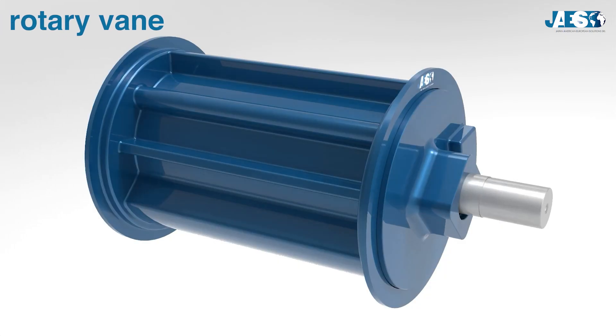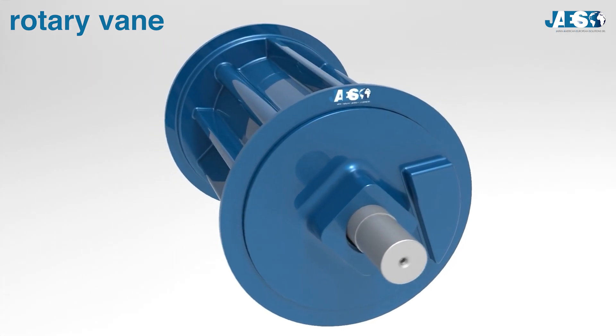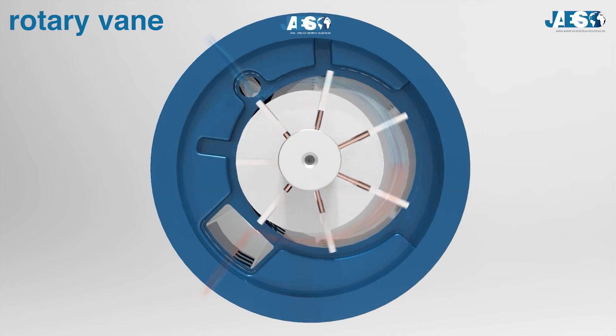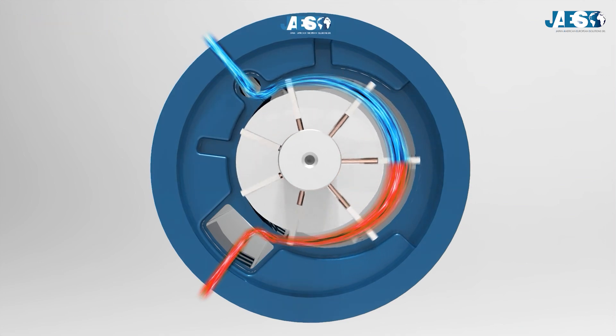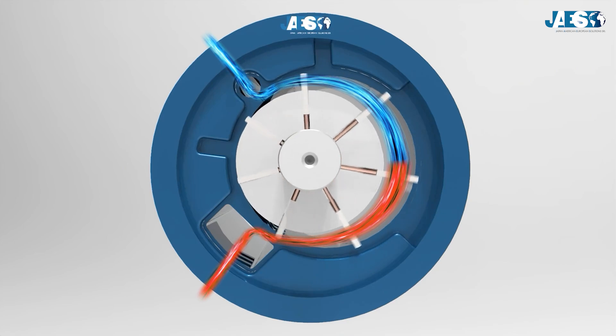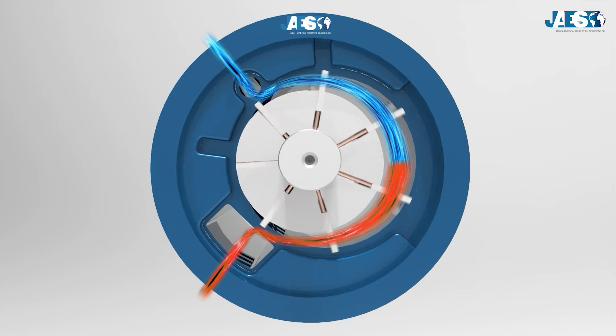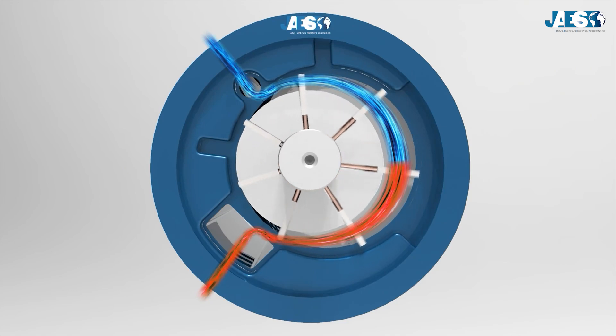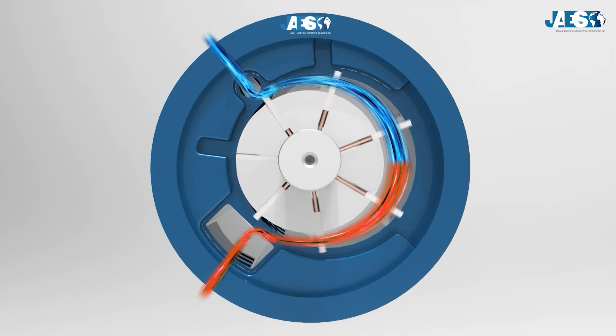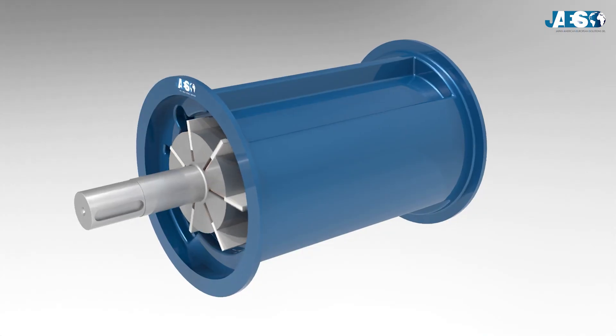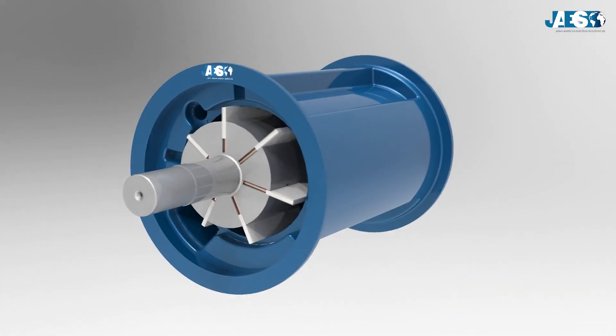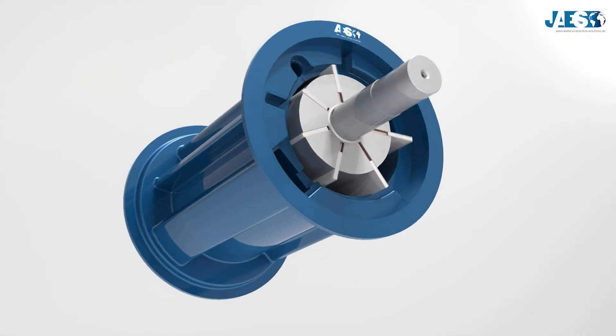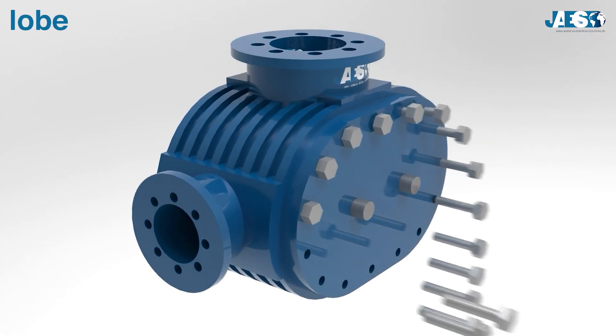Moving on, we come to analyze the rotary vane compressor. Here we have a very different type of product: a circular rotor is equipped with vanes which are pushed by springs to keep them constantly in contact with the walls of the circular cavity against which they slide. The rotor is not centered on the cavity, thus creating variable volume chambers at their maximum on the suction side and at their minimum on the delivery side, obtaining gas compression.